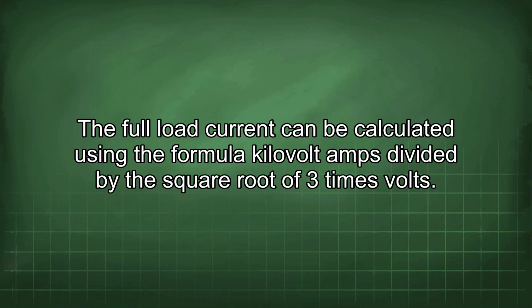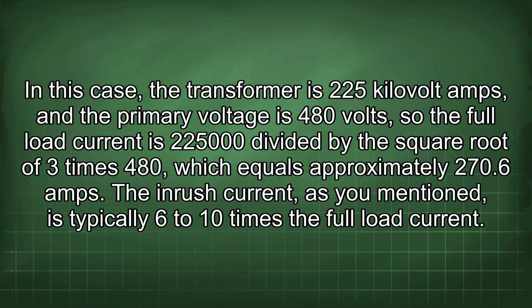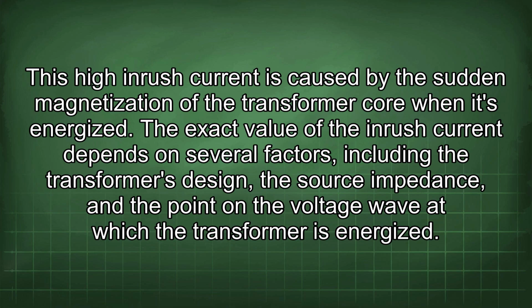The full load current can be calculated using the formula kilovolt amps divided by the square root of 3 times volts. In this case, the transformer is 225 kilovolt amps, and the primary voltage is 480 volts, so the full load current is 225,000 divided by the square root of 3 times 480, which equals approximately 270.6 amps. The inrush current, as you mentioned, is typically 6 to 10 times the full load current. This high inrush current is caused by the sudden magnetization of the transformer core when it's energized. The exact value of the inrush current depends on several factors, including the transformer's design, the source impedance, and the point on the voltage wave at which the transformer is energized.